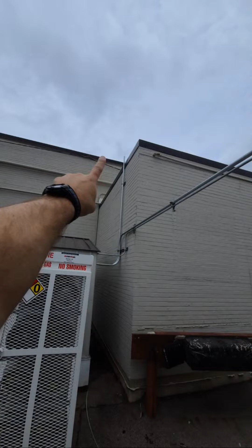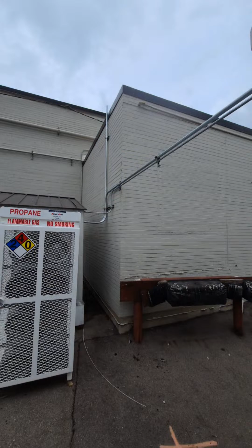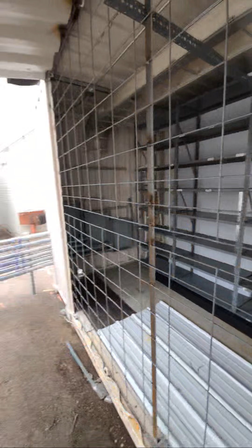The shed's kind of hooked up. It's not turned on, but it is semi-wired. So we've got conduit running from here, there's going to be three. One goes up to the top, that's for cameras and Starlink. And we've got 2 conduits coming in here for cameras and Ethernet. We're going to run a bunch of Ethernet, even if we don't plug it in, just so it's there and done. If it sits empty, it sits empty, but at least it's run in case we need to swap something, add something, or do something. So yeah, he got all that done. He just killed it.